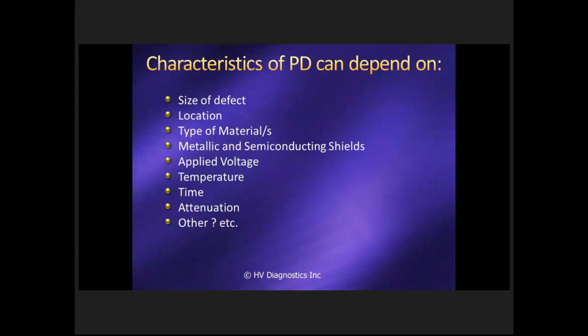Okay, so characteristics of a PD. As you can see, I've listed a whole series of different characteristics that can determine the size or the intensity of the PD. First, the size of the defect. Typically, if you use a void as a source of the PD, the bigger the void, the higher the PD spike. Then the location of the defect, in other words, where inside the cable it is located, closer to the outside shield or closer to the conductor.